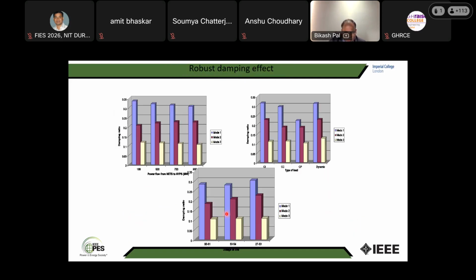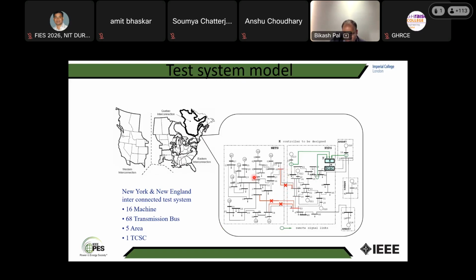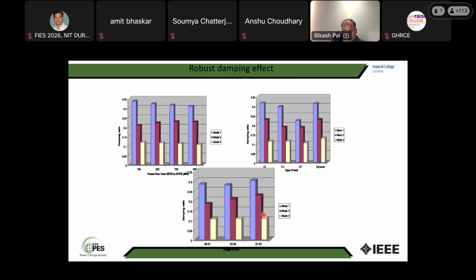So that mode, you can see here, this is the damping of that mode. 1, 2, and 3, that light blue, and then this red, or whatever you call this, and then this light yellow. So these are 3 modes, and if you look at the damping ratio, they are more than 0.1. So that is good. And what is changing? Changing is the power flow between area 1 and area 2, 100 megawatt to 900 megawatt. Why is that? So these are the lines. Area 1 to area 2, if the power flow changes in this line, so the G will change, and you have designed that control K with additive uncertainty. So that's why robustness is built up. So you see that you have a good damping.